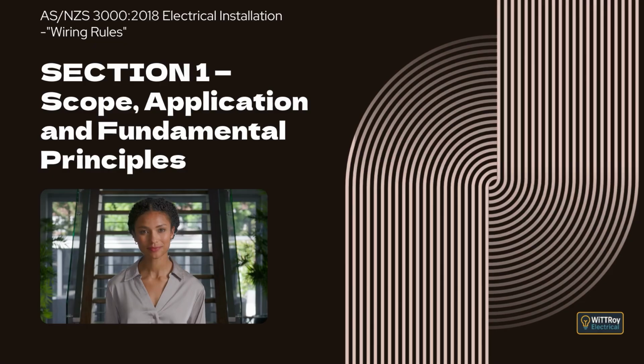Clause 1.5.6.2 explains that RCDs are acceptable for fault protection. If a fault causes current to flow to earth, the RCD detects the imbalance and switches off the supply quickly. This reduces the chance of electric shock in a fault situation. Clause 1.5.6.3 explains where RCDs must be installed. They are required for socket outlets, lighting points, handheld equipment, and many wiring systems.